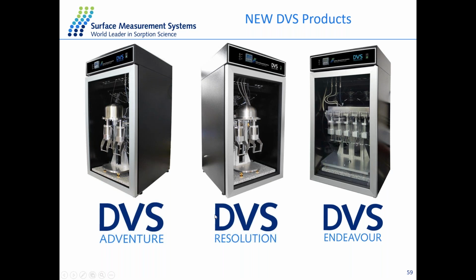DVS Resolution will allow you to run experiments in water and/or organic solvents, so single component and multi-component experiments. And DVS Endeavor can run experiments in water plus organic solvent, but it's a multi-sampler system, which means that you run 5 experiments at the same time rather than running 1 each time.